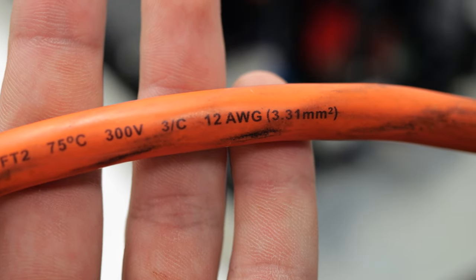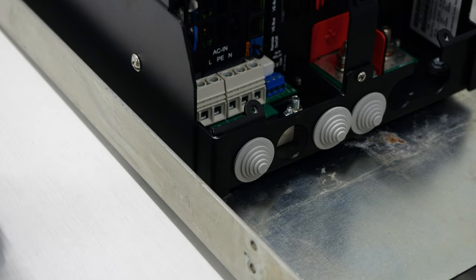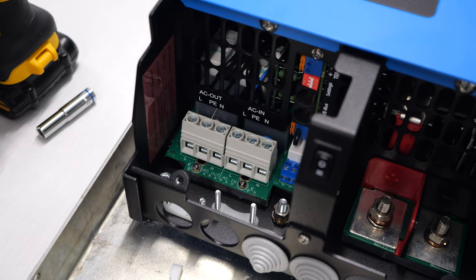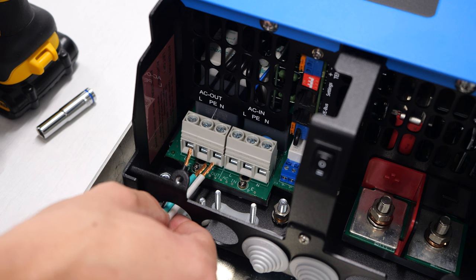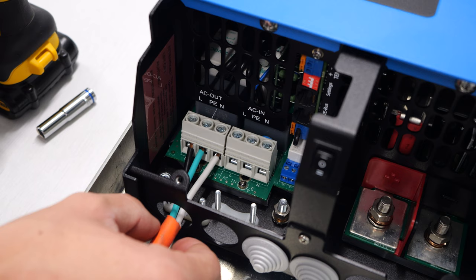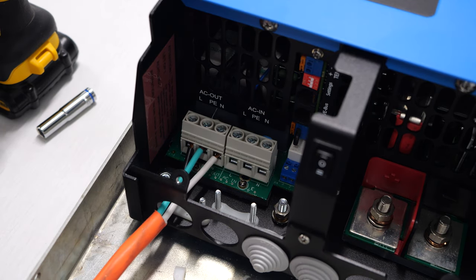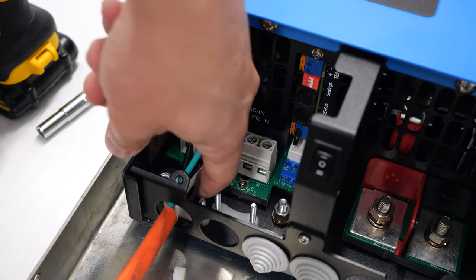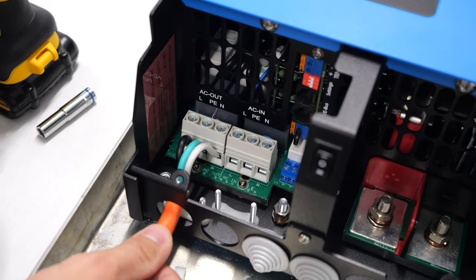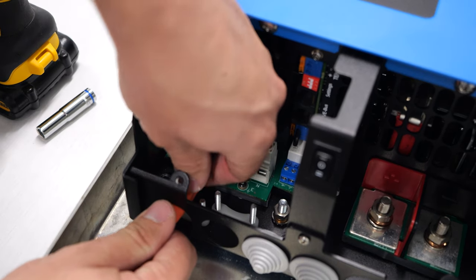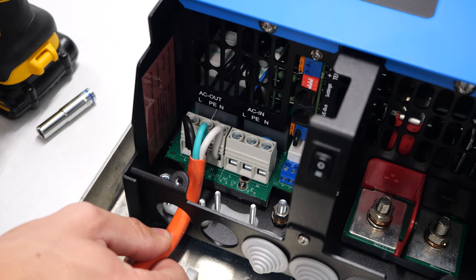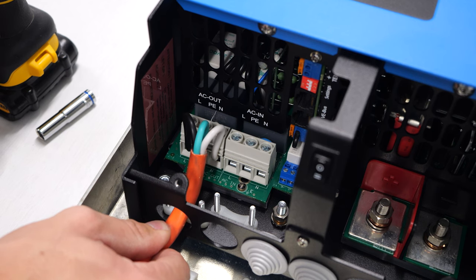This cord is a three conductor, 12-gauge cord, so we're good for 20 amps. We should have no issue carrying the full output of this inverter or bringing the full input while the batteries are charging. I removed the top half of these clamps entirely so I can just freely shove the wire in. I typically like having a service loop. I'm going to get these wires in here and get the screws tightened down.